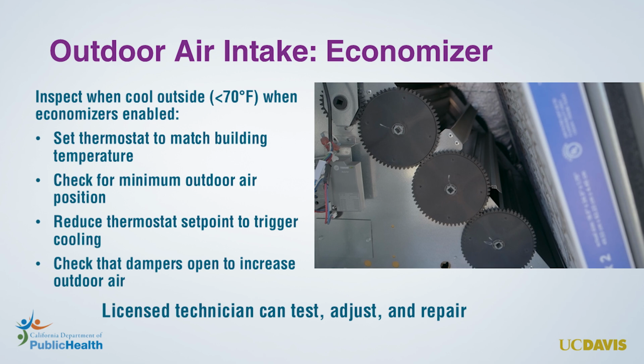This happens when the control signal gets wired backwards or programmed incorrectly in the control system. Document any economizers that are not functioning or functioning incorrectly. A licensed technician can test, adjust, and repair economizers and ensure the controls are communicating correctly with the mechanical system.